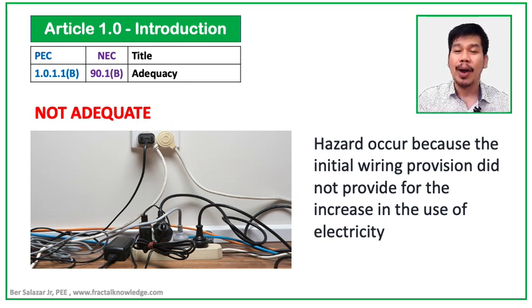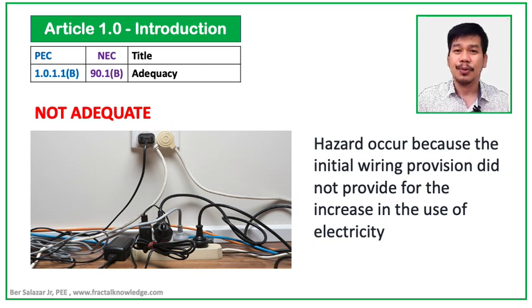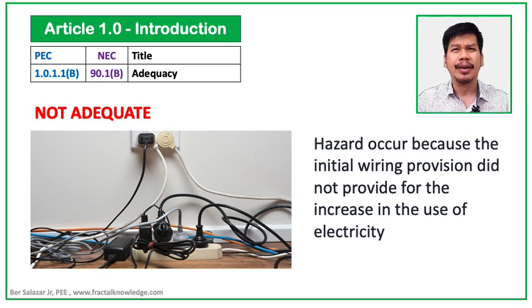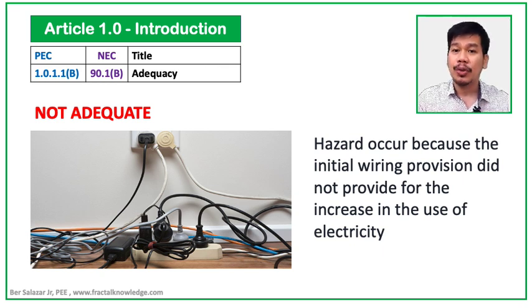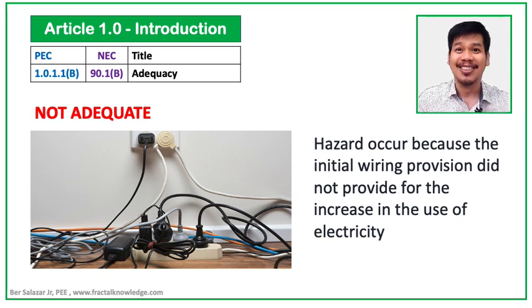Hazards occur because the initial wiring provision did not provide for the increase in the use of electricity, and therefore the wiring system becomes overloaded. You can see this common in a store or with electric appliances at home or in some offices. Provision for the increase in load was not projected due to changes in activity in the use of the area. However, in my years of experience, I saw designers compute too much allowance for load growth. In terms of economics, the initial investment is high and the owner shoulders all the costs, but over the years, the factor on load growth was not used. What we need to do is design an electrical system that is adequate, and it should be stated in the design brief, which is not included in the electrical plan. You should ask that to the electrical designer.